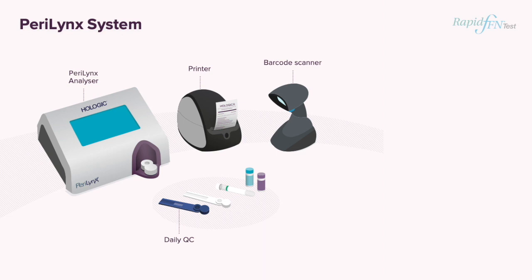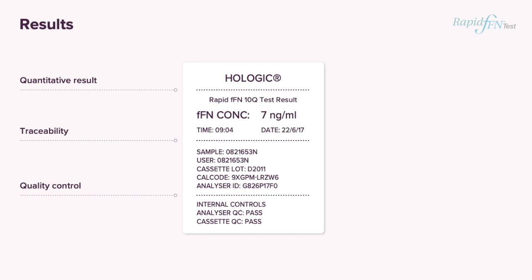This affords greater flexibility as samples can be collected and are stable for up to eight hours at room temperature. Only samples with no contraindications requiring analysis will utilise a fetal fibronectin cassette. With less than 10 minutes analysis time, you will receive a results label, which details your quality control, traceability such as user ID and patient number, and your quantitative fetal fibronectin result.